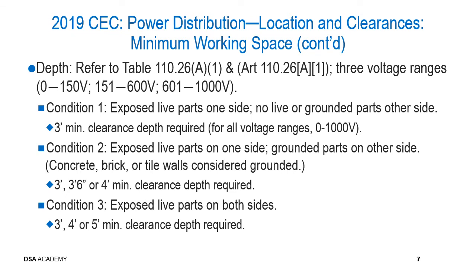Let's continue now and discuss some of the details with respect to the minimum working spaces that are required around power distribution equipment. With respect to the minimum working depth that is required in front of panels, you can refer to Table 110.26(A)(1) and Article 110.26(A)(1). And there are basically three voltage ranges that we're concerned with that actually determine the parameters for safe minimum working spaces. And those three voltage ranges are 0 to 150 volts, 151 to 600 volts, and 601 to 1000 volts.